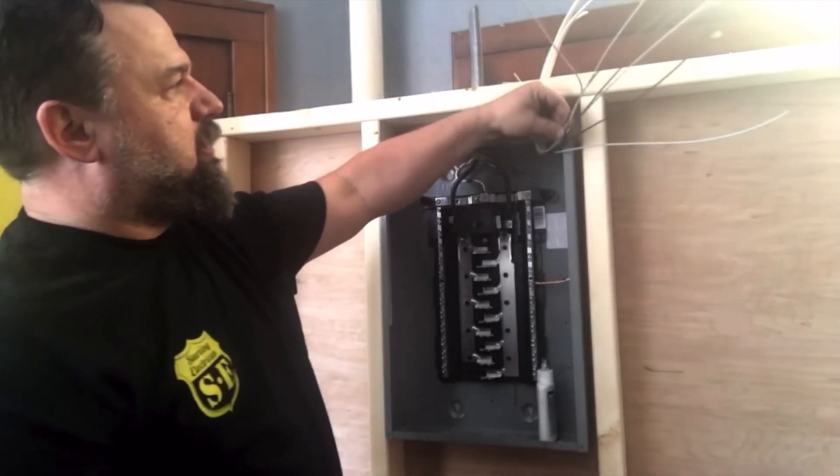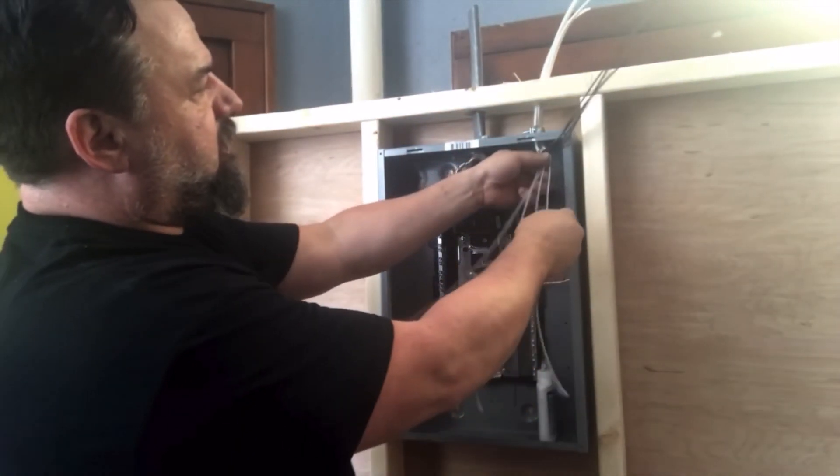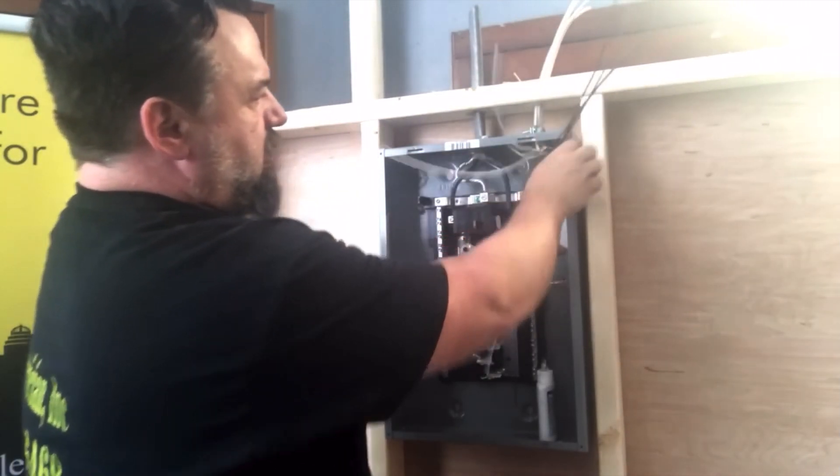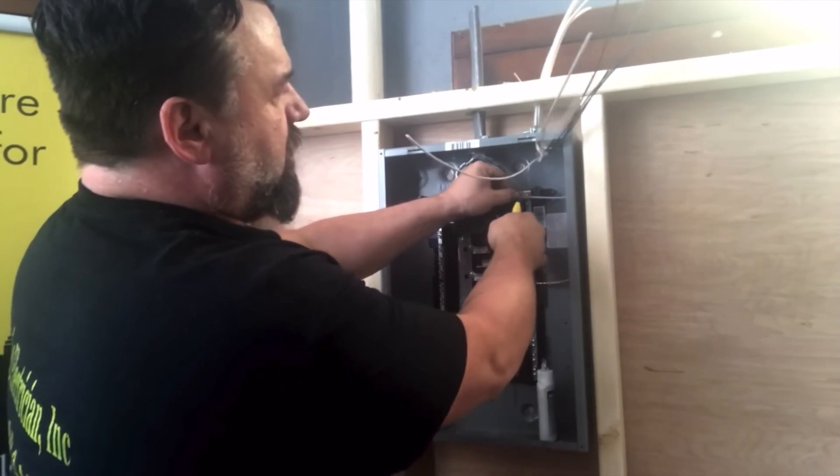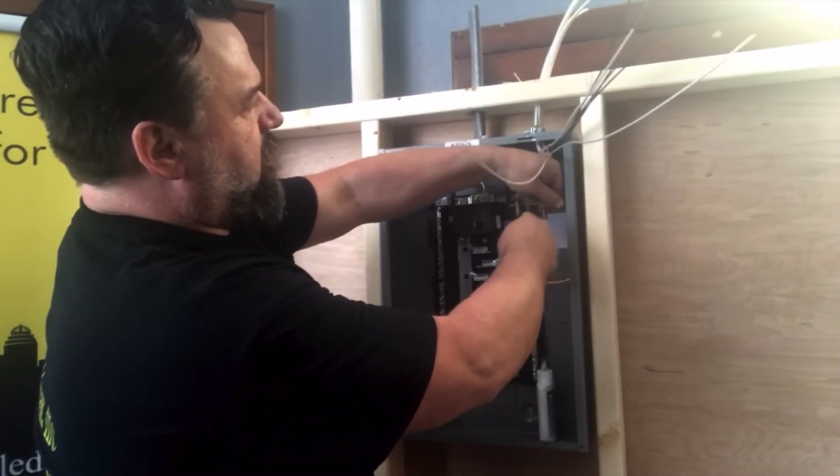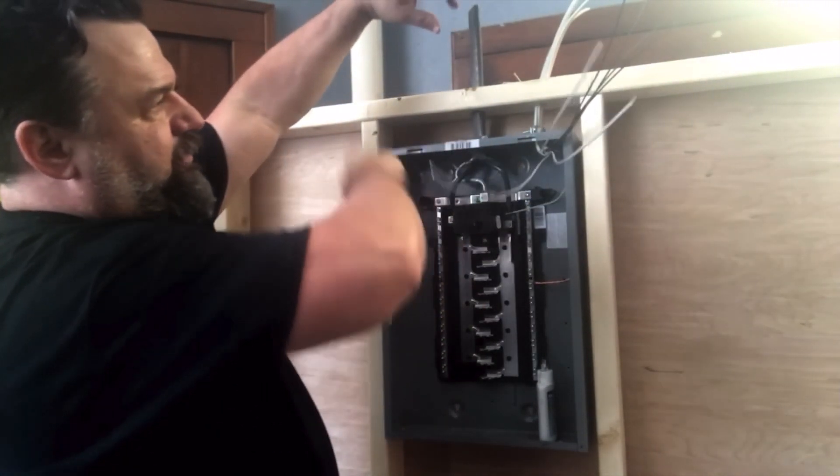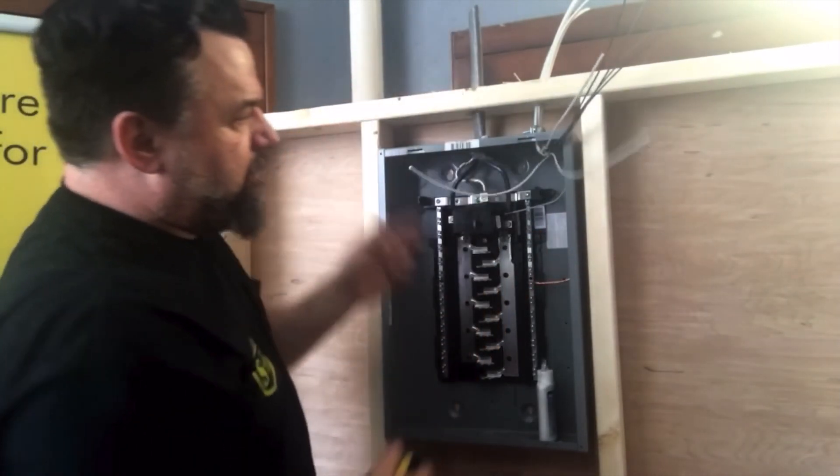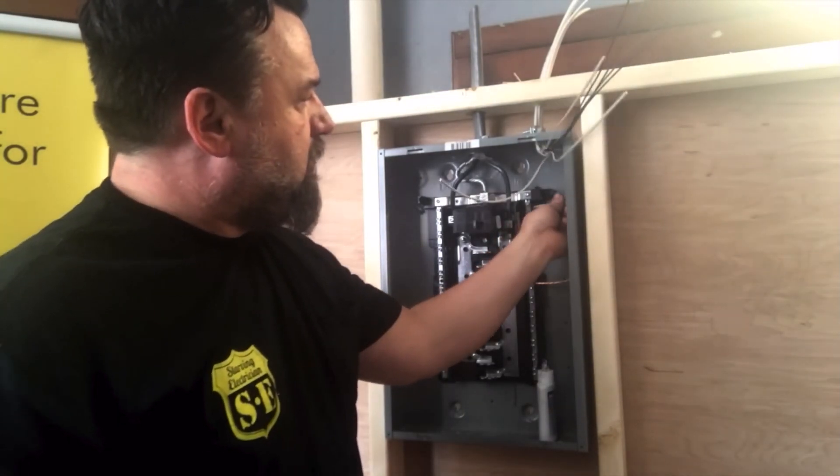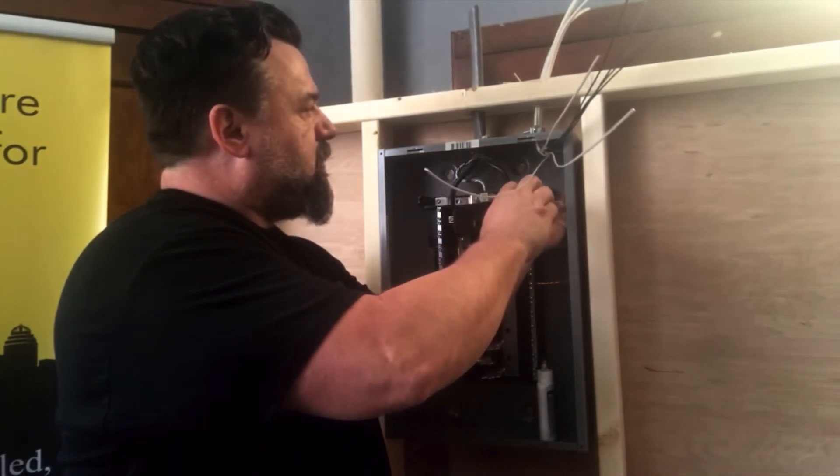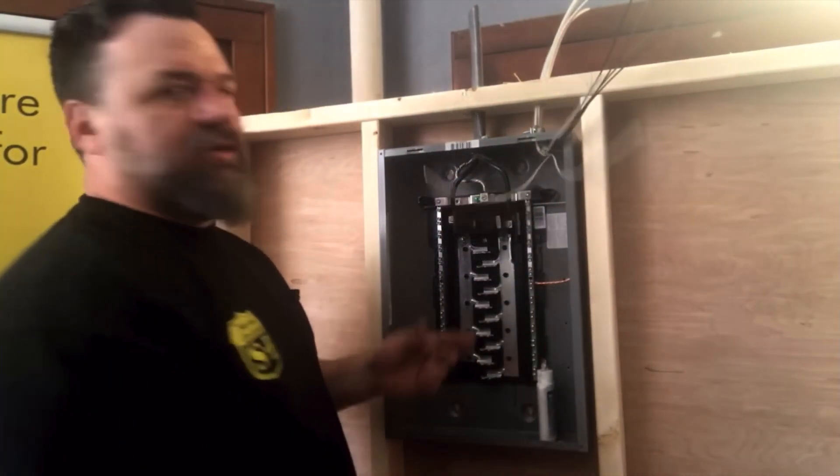Now, we have our neutrals. Neutrals have to be landed individually in each one of these lugs because they are current carrying conductors. This is AC, alternating current. AC goes from the hot to the neutral, back and forth. It alternates. So if there's a light on, it's going to go through the light and back to the neutral into here. You can pull this off and you get zapped by it because now it's carrying current. Each one has to be individual under each lug because two current carrying conductors can produce heat.